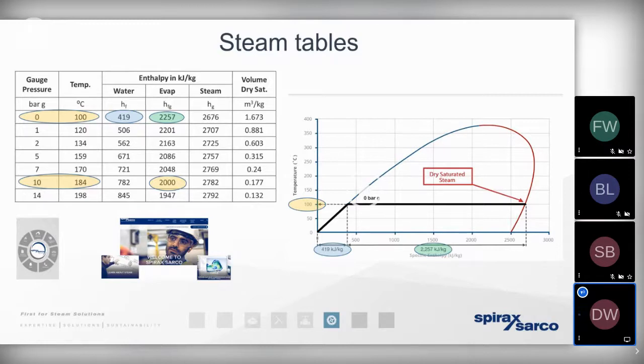So first of all, we can see that there's more useful heat energy. There's more latent heat present in steam at a lower pressure. So if we take the example of 10 bar gauge, you can see the enthalpy of evaporation, or the latent heat, that's the energy that can be used by the process, is far, far greater at a lower pressure than it is at a higher pressure. So we've got an increase in efficiency and heat transfer speed by reducing the pressure at the process.